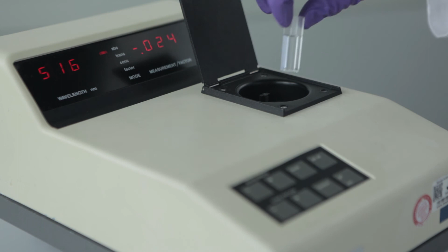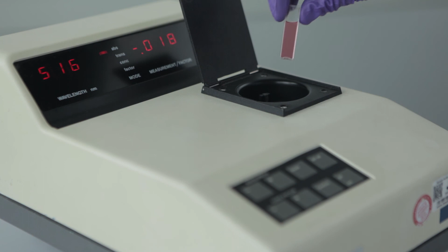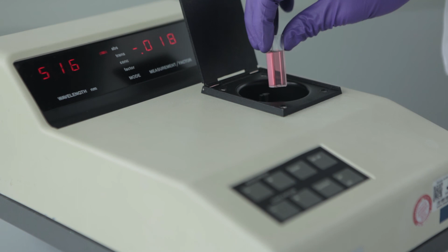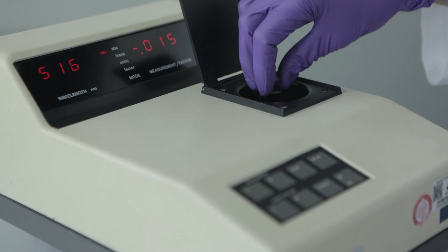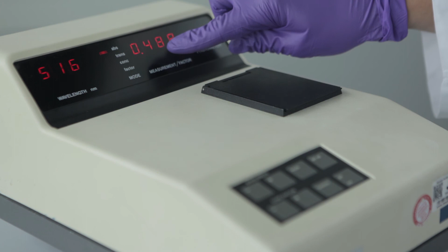We open the lid and remove the blank. We then place our sample. We place the cuvette in the same manner as the blank, so with the clear sides in the same direction as the beam of light. We close the lid again. And then we see our extinction on the display, which is 0.488.